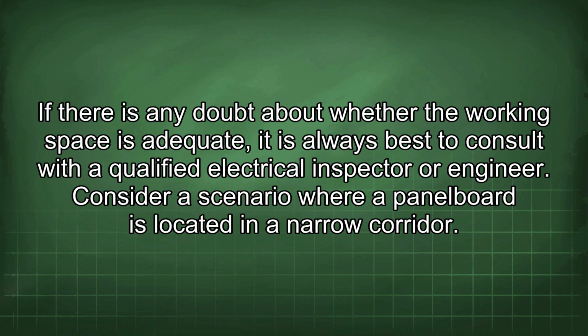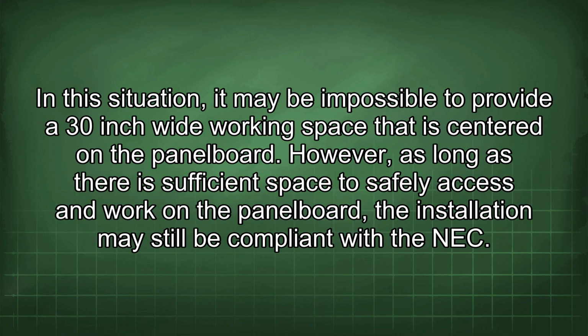Consider a scenario where a panel board is located in a narrow corridor. In this situation, it may be impossible to provide a 30-inch wide working space that is centered on the panel board. However, as long as there is sufficient space to safely access and work on the panel board, the installation may still be compliant with the NEC.